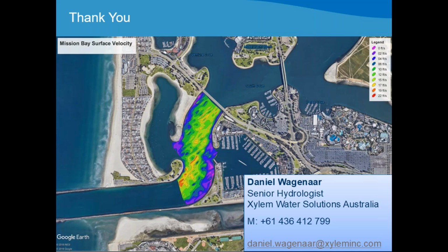I can't indicate to you that the 16 would be enough or not enough. What I would recommend is perform an in-depth analysis using either Extrap or QRev and look at the velocity profile. If you see a bend back, that could be, but then again, you need to verify if there was no wind blowing upstream as well, and the aspect ratio, if that is applicable or not. So there are certain factors that you need to evaluate before you make a decision. So it's very difficult to give you a single answer on this, because you need to evaluate all the different factors involved.